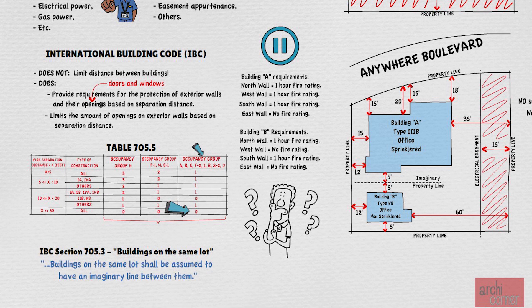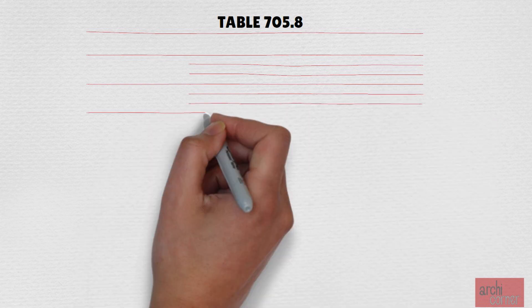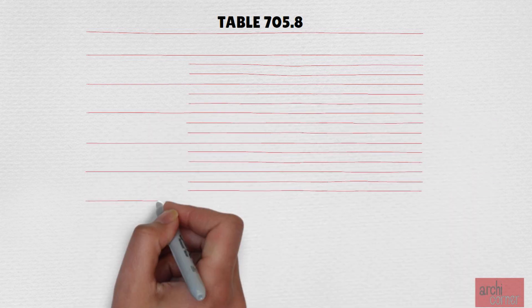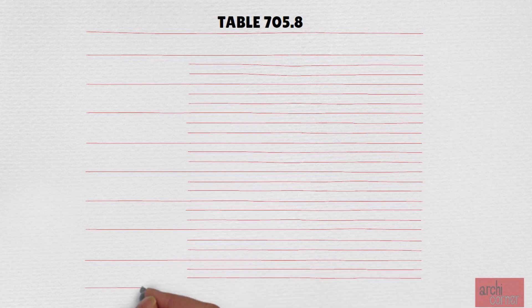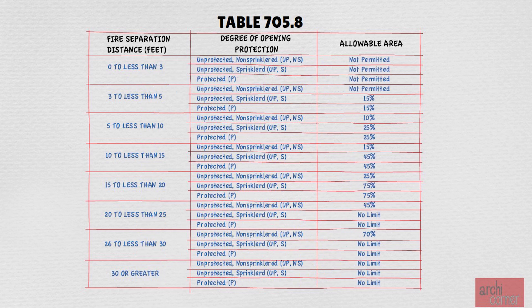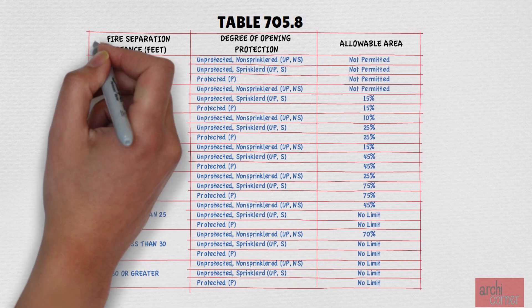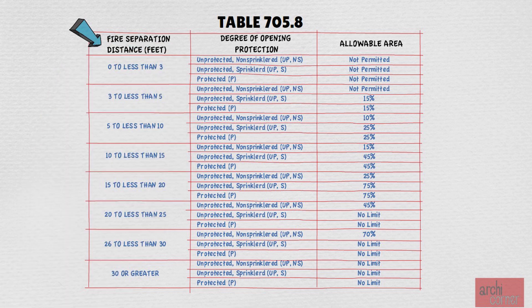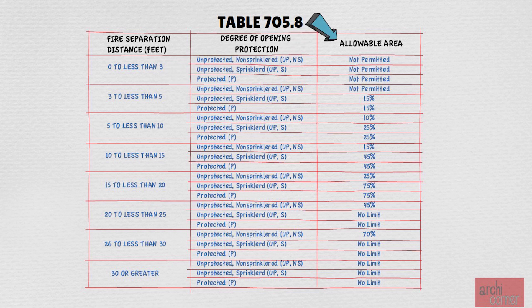But how about openings? For that, we must look at Table 705.8 of the IBC. A portion of it is shown here, and just like the last table, there are footnotes missing, so please be sure to look at the actual table in the IBC. As you can see, the first column determines the distance of the building to the property line. The second column provides options for unprotected non-sprinklered, unprotected sprinklered, and protected. Once you know the distance and type of opening protections, the third column lets us know what percentage of the wall is allowed to have openings.